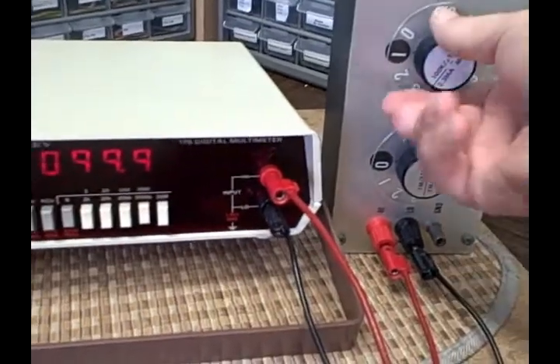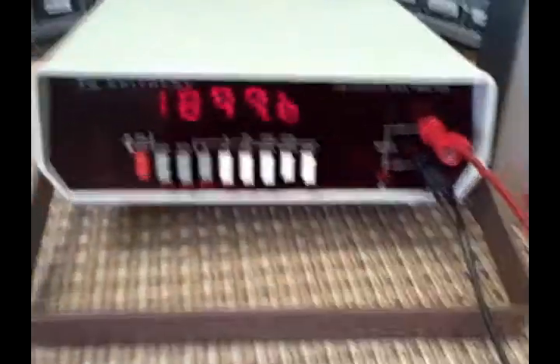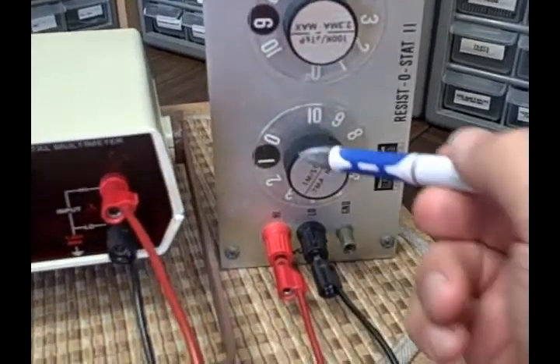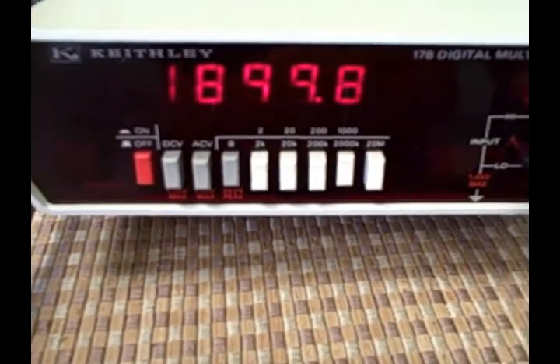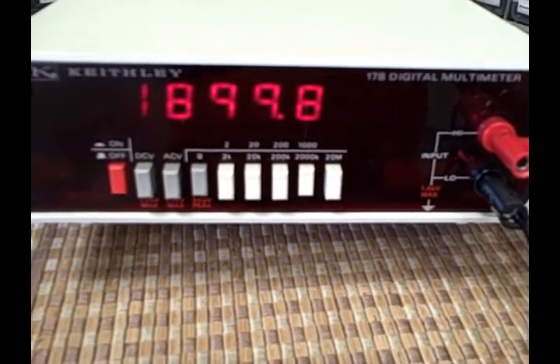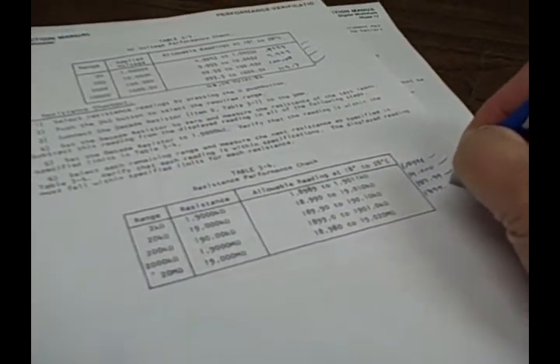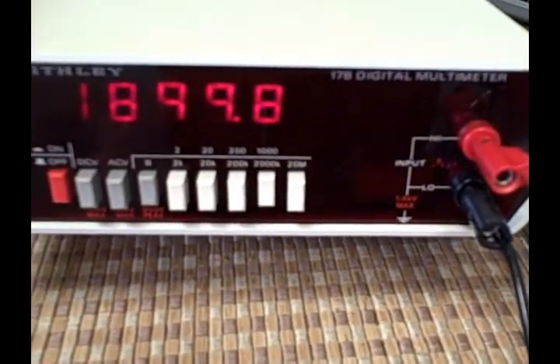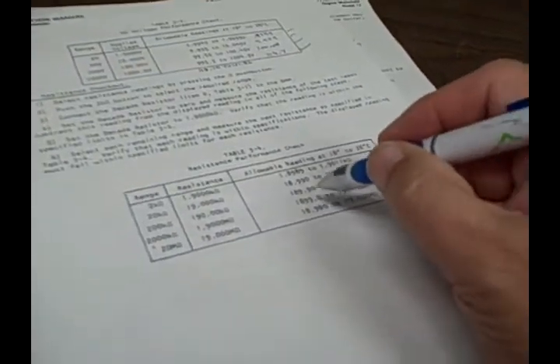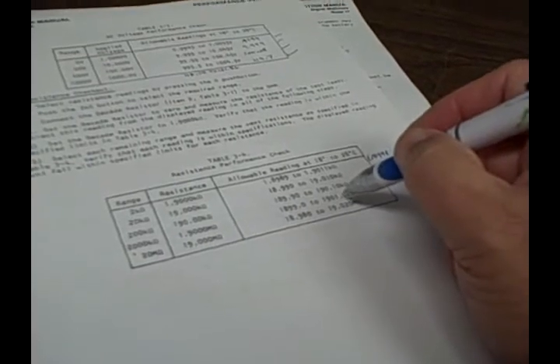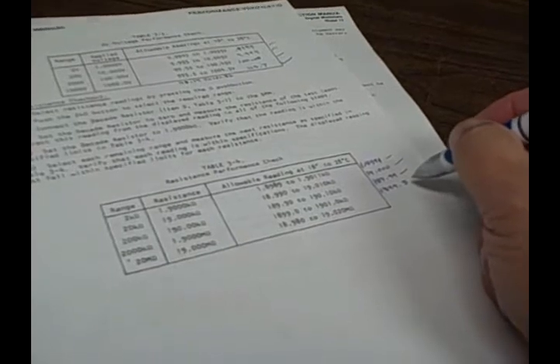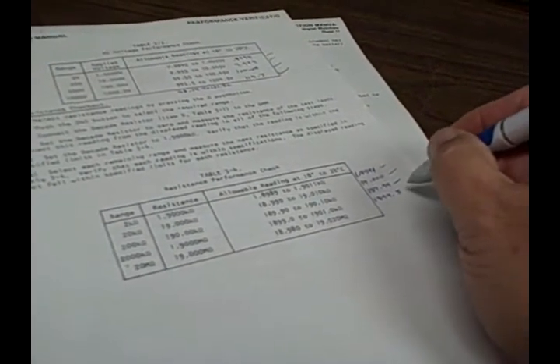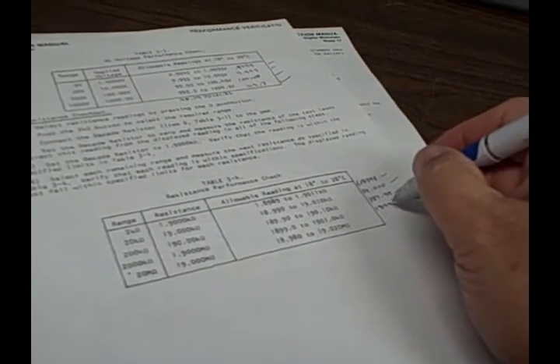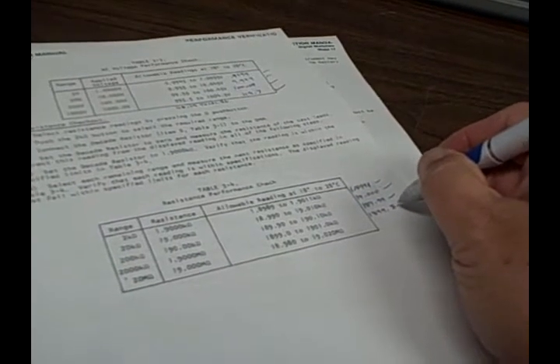And we've got to dial in 1.9 megohms. Okay, there's 1,900,000 and all zeros. So we're reading right now 1899.8. And we're flashing to a 9 now, so it's maybe a little better, but I'll keep it at 8. We'd be good if we were at 1899.0 to 1901.0. At 1899.8, we are right in the middle. That would be thousands, so this is hundreds, so we're less than 200 ohms off of perfect. So that came out good.